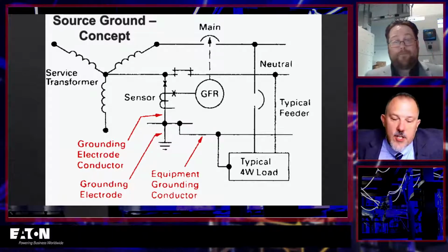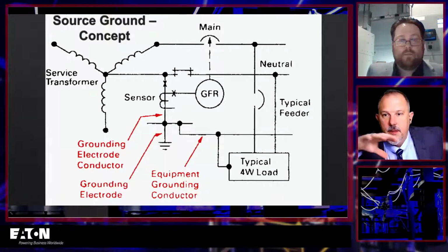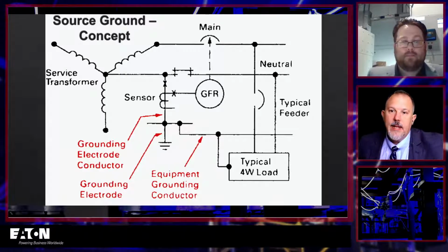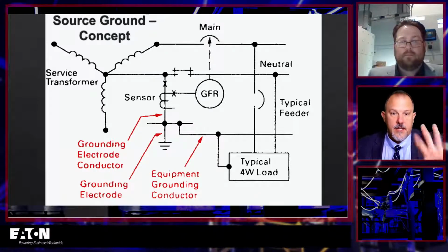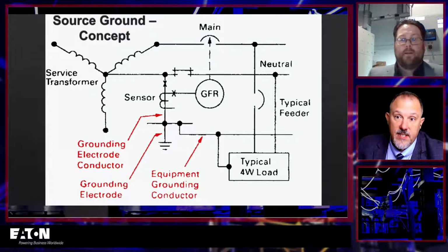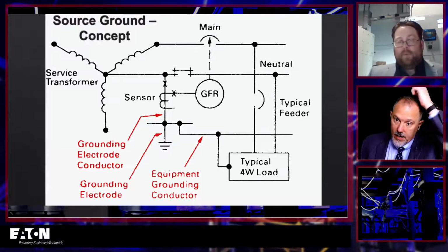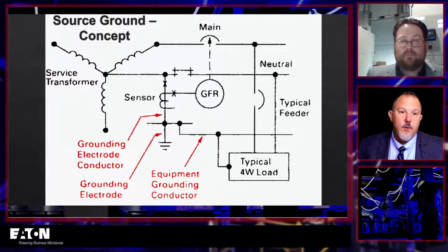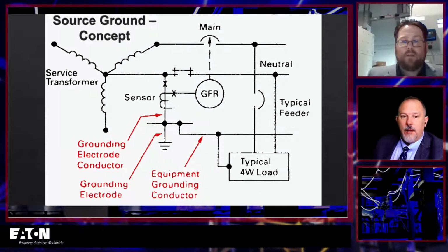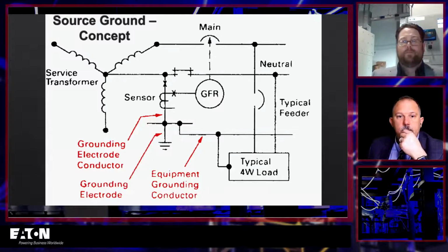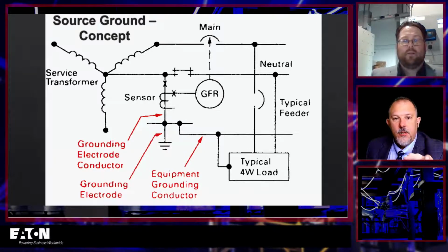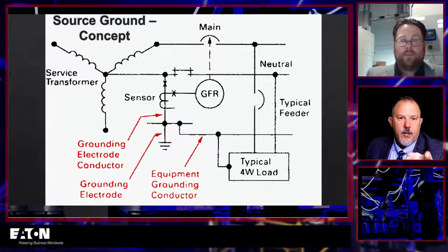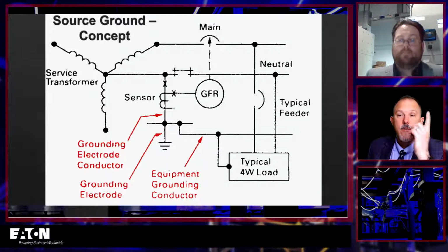So let's talk about all the different components in the system. I know you have the relay itself, and in some cases the CT and the relay are all part of the circuit breaker itself, right? Yep, but not in all cases. What I'm showing here is a Y grounded system, so this will be your typical system. I noticed that in this case there's a CT in the ground, so you're monitoring the grounding electrode conductor going to ground.